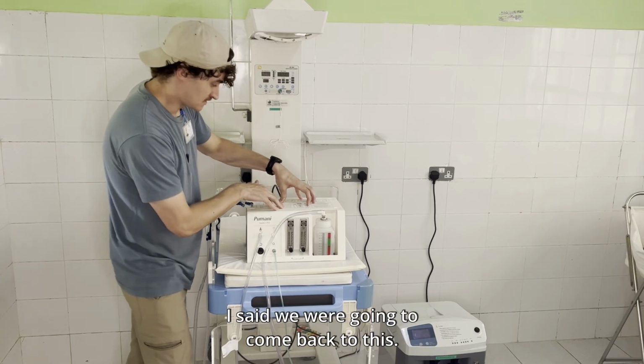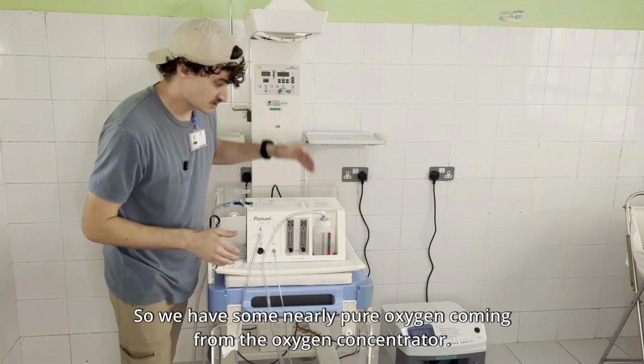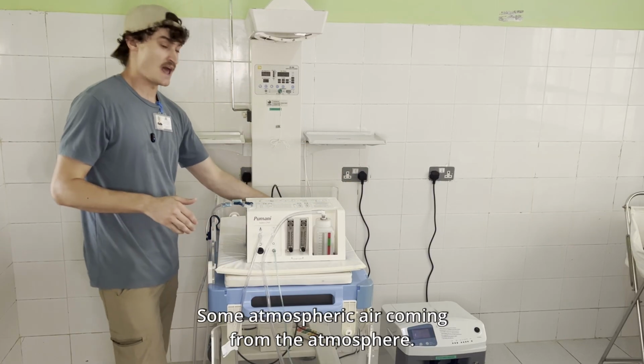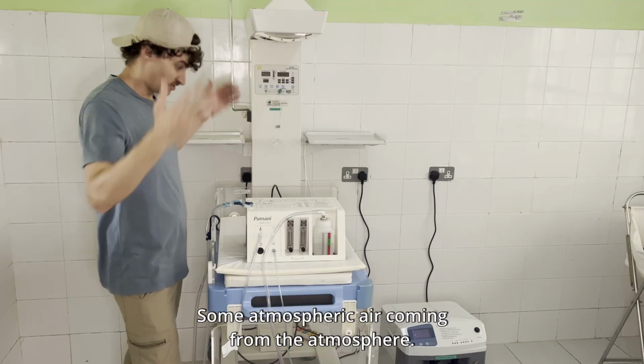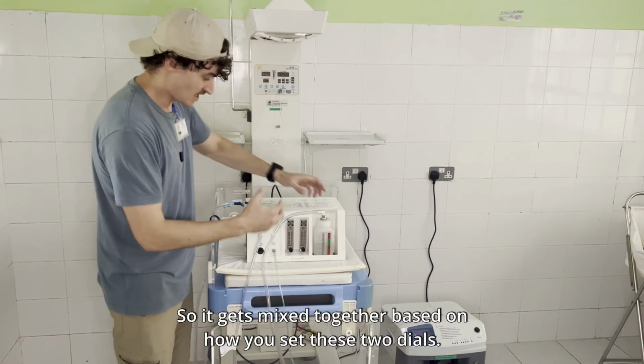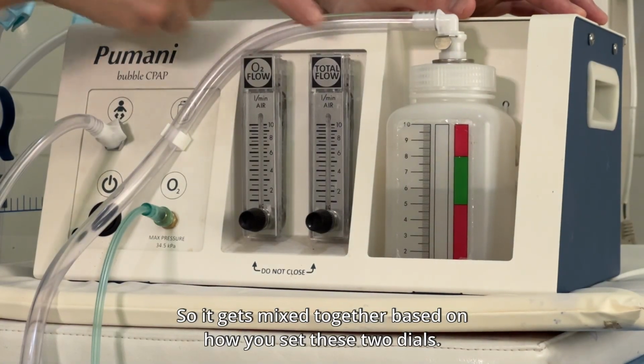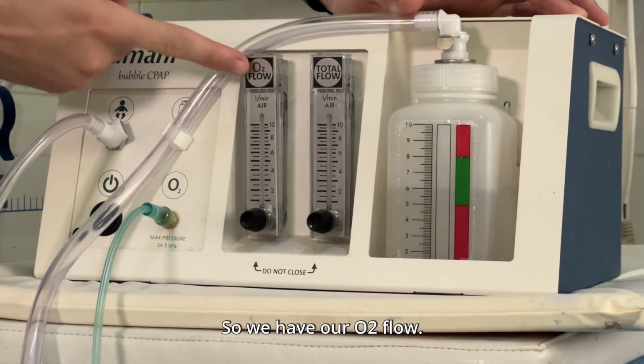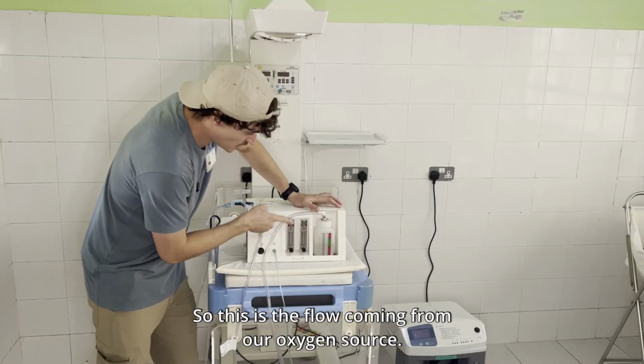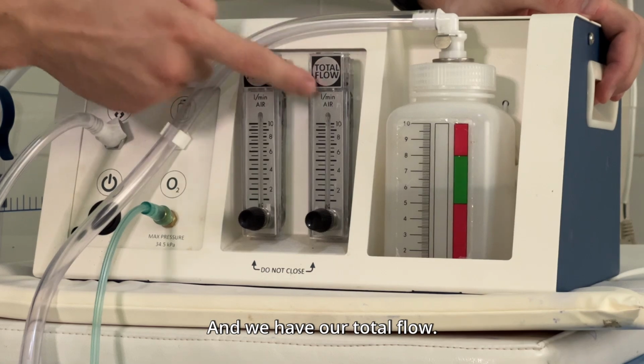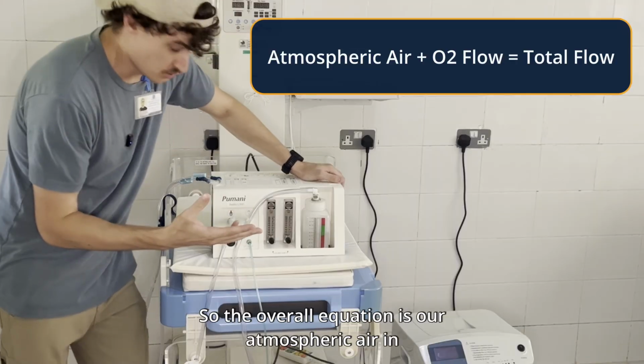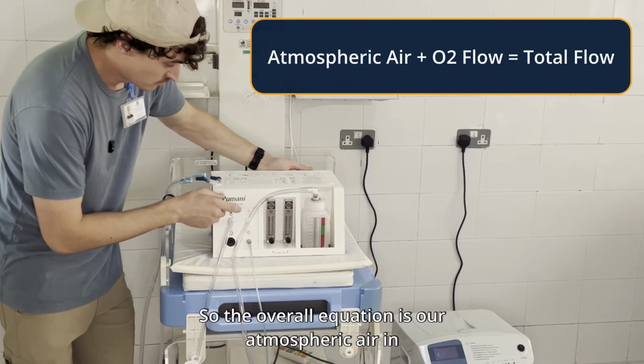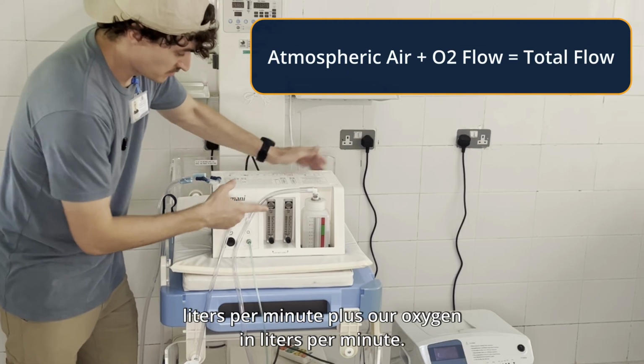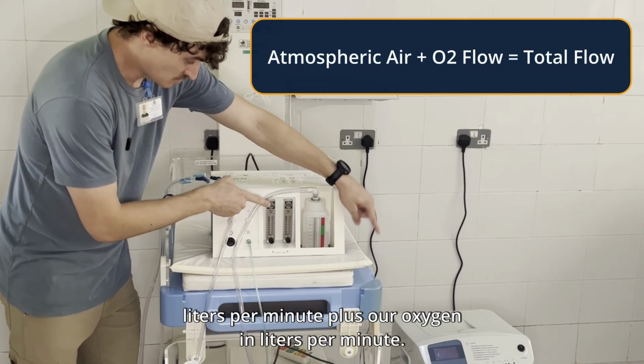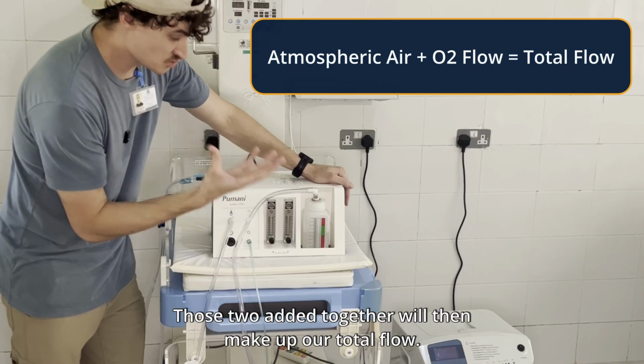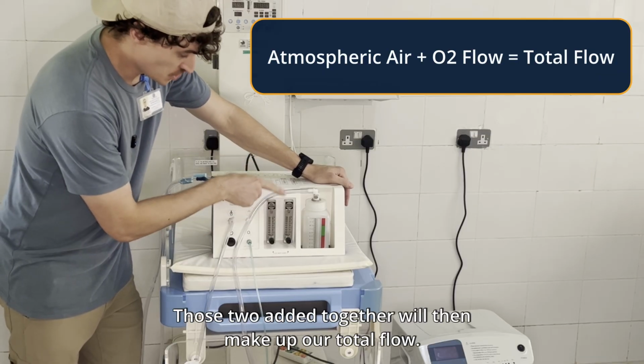I said we were going to come back to this, right? So we have some nearly pure oxygen coming from the oxygen concentrator, some atmospheric air coming from the atmosphere, right? So it gets mixed together based on how you set these two dials. So we have our O2 flow, which is the flow coming from our oxygen source, and we have our total flow. So the overall equation is our atmospheric air in liters per minute plus our oxygen in liters per minute. Those two added together will then make up our total flow.